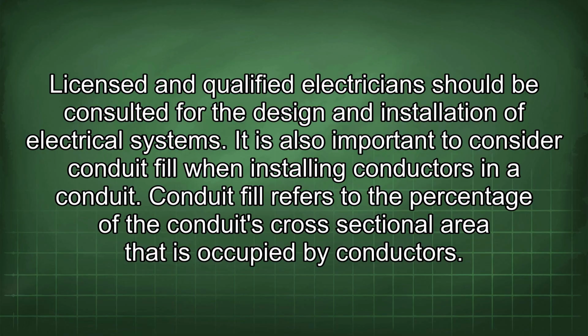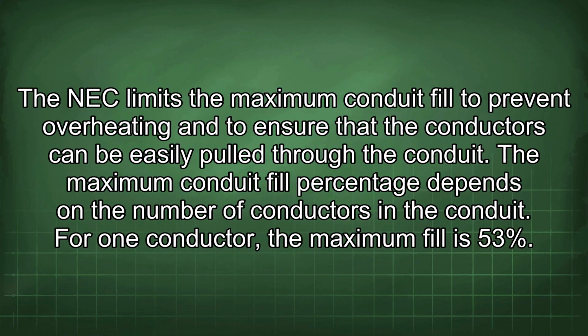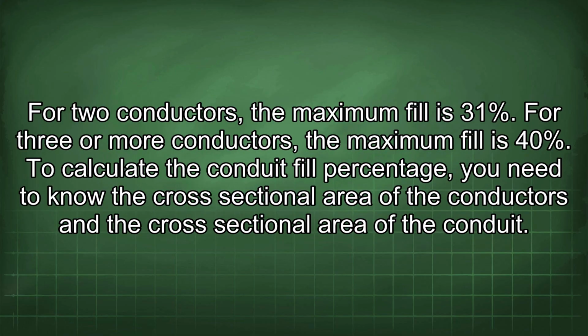It is also important to consider conduit fill when installing conductors in a conduit. Conduit fill refers to the percentage of the conduit's cross-sectional area that is occupied by conductors. The NEC limits the maximum conduit fill to prevent overheating and to ensure that the conductors can be easily pulled through the conduit. The maximum conduit fill percentage depends on the number of conductors in the conduit. For one conductor, the maximum fill is 53%. For two conductors, the maximum fill is 31%. For 3 or more conductors, the maximum fill is 40%.